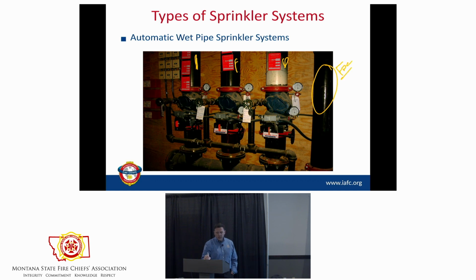Okay? So this goes somewhere else, right? And it's what connects, right? The water to the water system's back here. And what's not in this picture is another series of valves in something called a backflow device. Okay, so it's got usually OS&Y, might have butterfly valves. There's a silver thing in the middle. That's the backflow device and your main system control. If I shut that off, what does it do to all the risers? Shuts them off. Now, we teach firefighters that when we have a fire in a commercial setting, only shut off the floor, only shut off the riser in the fire-affected area, correct?